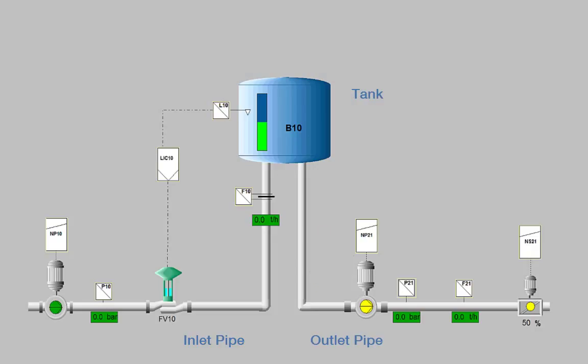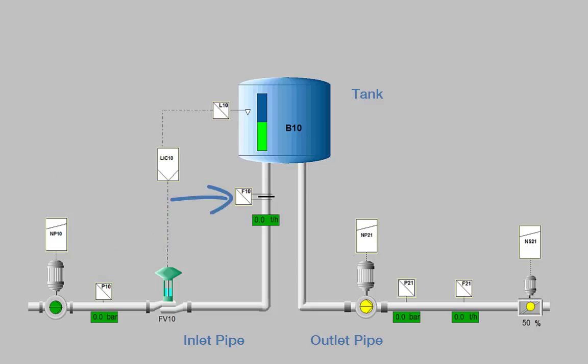The inlet pipe is equipped with a pump, a pressure transmitter, a valve with a positioner and a flow transmitter. The tank itself is equipped with a level indicator. This feeds a loop controller which controls the set point of the positioner according to the specified water level of the tank.